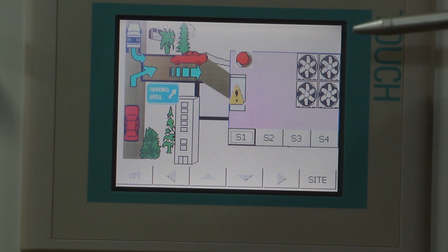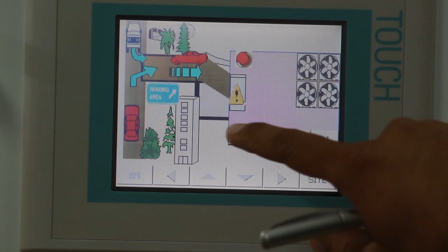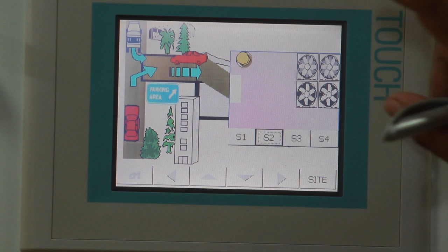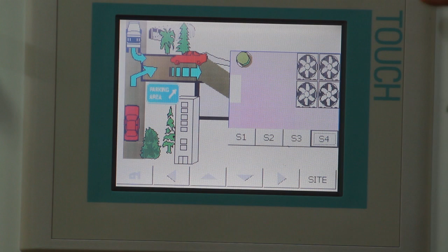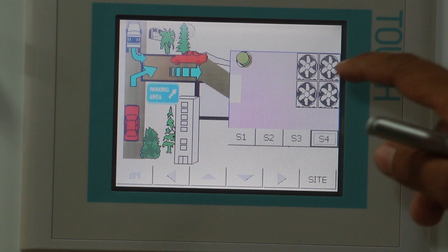When none of the fans is in working mode, a red light and an alarm appear. This is the condition of emergency, and no vehicle is allowed to enter inside the parking. When we switch on one fan, the red light appears. It means there is no proper ventilation inside the parking. But when 2 fans are in working mode, the yellow light appears. When 3 or more fans are in working mode, the signal is green, meaning there is proper ventilation inside the parking, and vehicles are allowed to enter inside the parking.